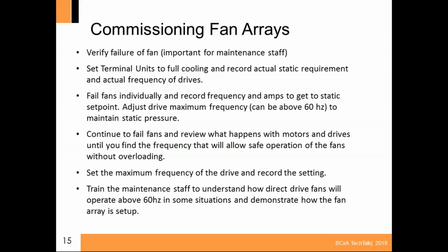Big one, the last one is, man, you've got to tell that maintenance staff exactly what you're doing. Educate them on how direct drive fans are. What I like to do is put the drive to show the load side and show them how the voltage and amperage react differently at part load than they do at full load. And I try to train them on that so they get an idea of what's happening with the drive. And then I start saying, if we go above 60 hertz, this is what happens. We're just spinning faster. And I try to get them through that whole idea about a 22-inch fan being at its most efficient at about 2,200 RPM instead of at the 1,800, which the motor is physically fixed at.